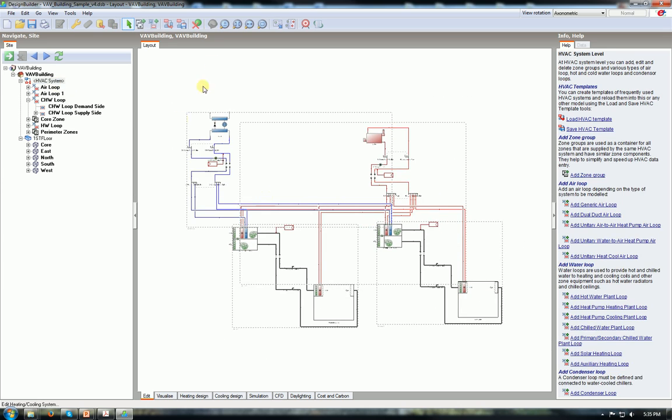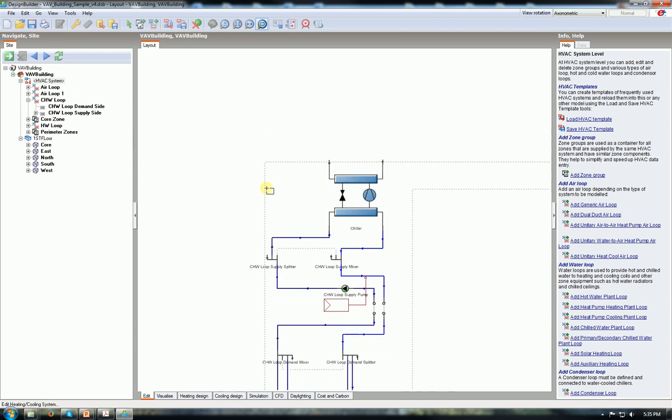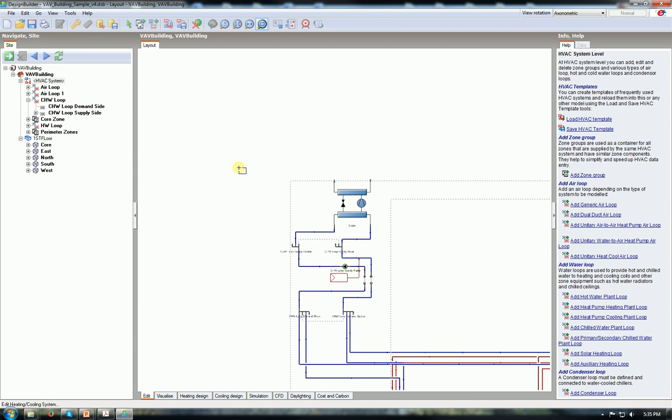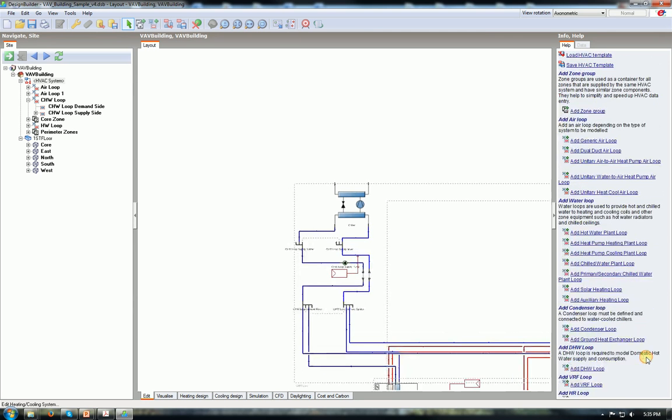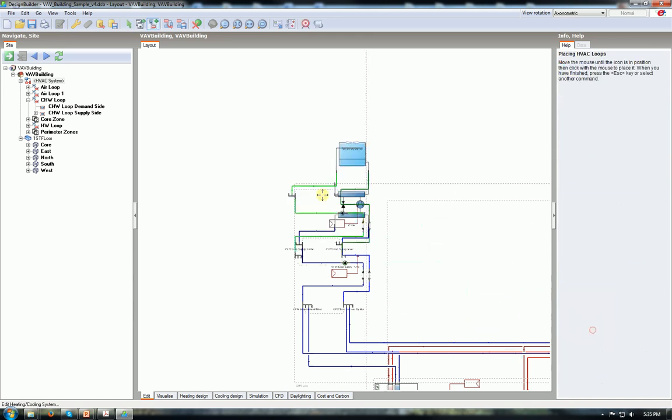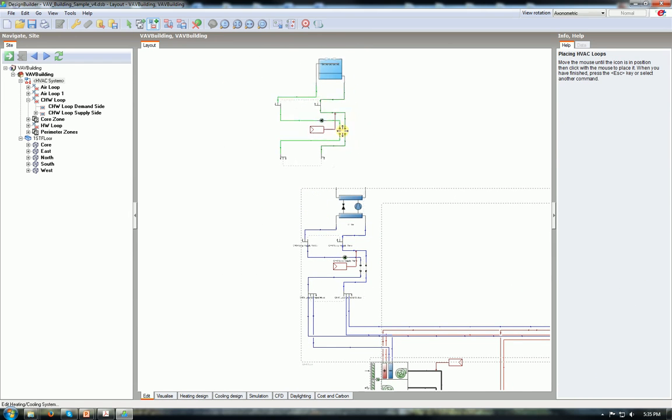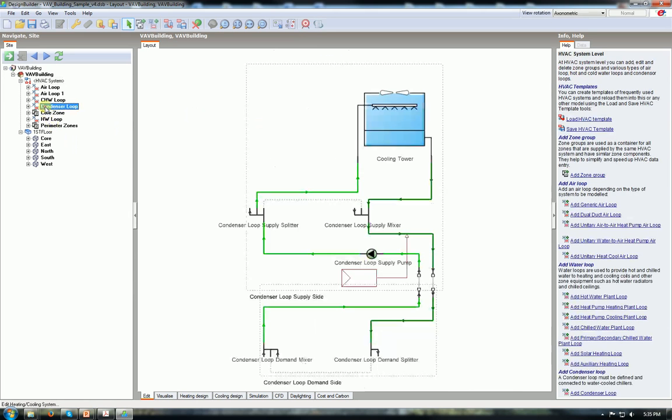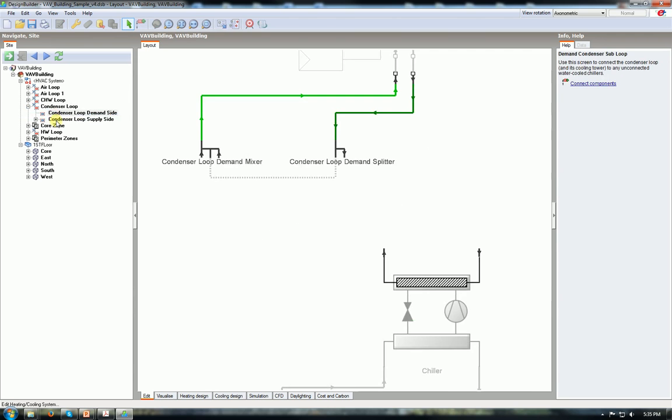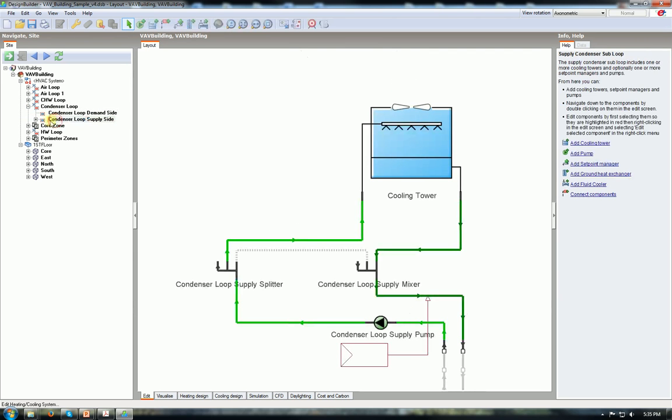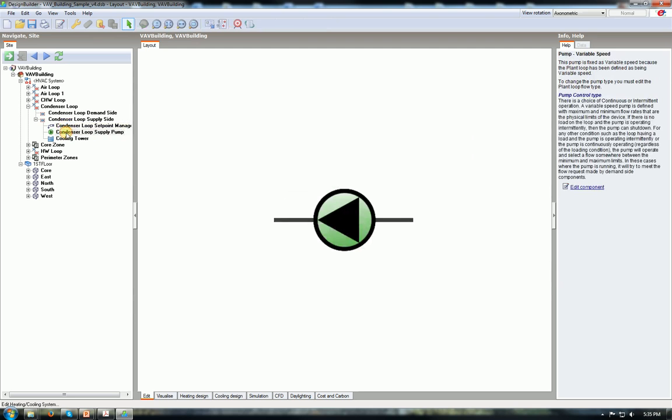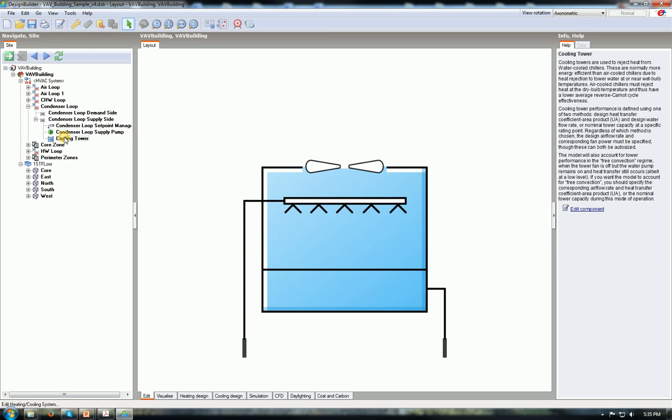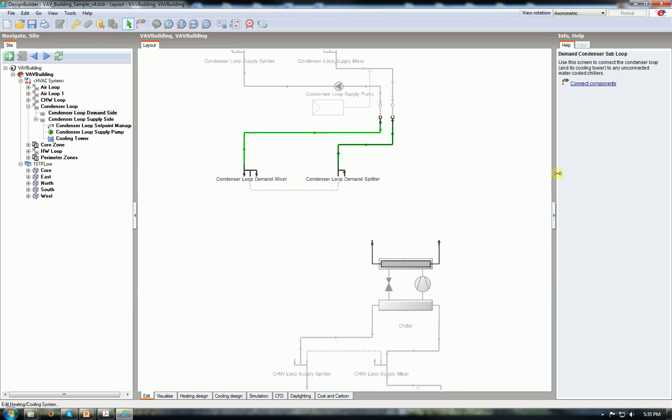Now HVAC system, but something is missing. What is missing? We need the condenser loop. We need the cooling tower. These ends should be connected to something and they are waiting. And we need the condenser loop to finalize the entire water cool chiller system. So I will say add condenser loop. Here is the condenser loop with all the components. Place it any place you would like to be placed. Condenser loop and the components - we have the demand side system, we have the supply side systems. Underneath the supply side system I have a setpoint manager, I have this pump, and I have the cooling tower, the final elements.